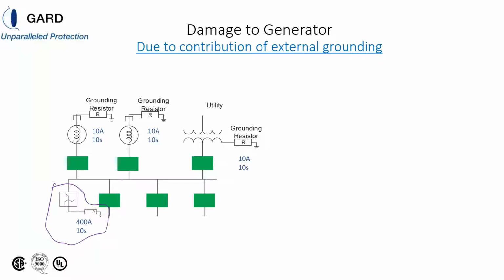And the only thing you need to ensure is that 400 amps is greater than or equal to the capacitive charging current of the system, and we're going to discuss that a little later. So if you have a stator fault winding in this particular scheme, your fault current is going to be 420 amps, resulting in 861 watt seconds of energy being dissipated in that stator fault winding. When the generator isolates, you could see that there's only a 10 amp resistor left in the circuit, so it limits the fault damage to 21 watt seconds, and your total is 882 watt seconds.